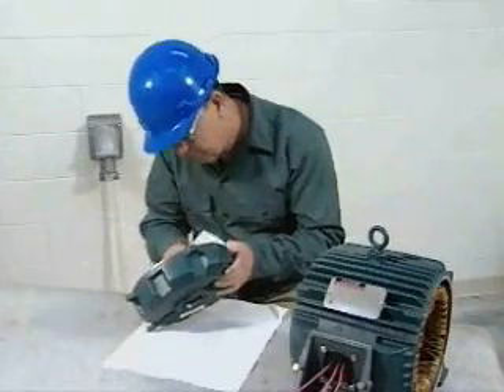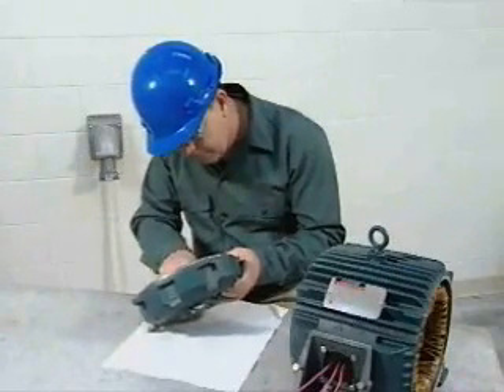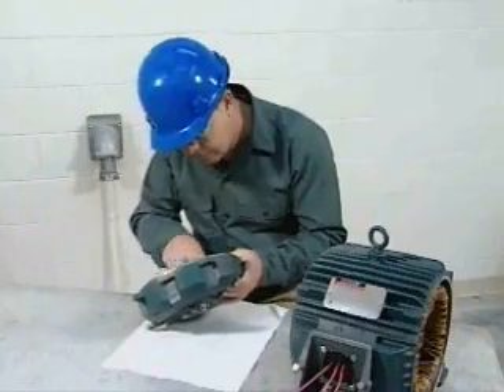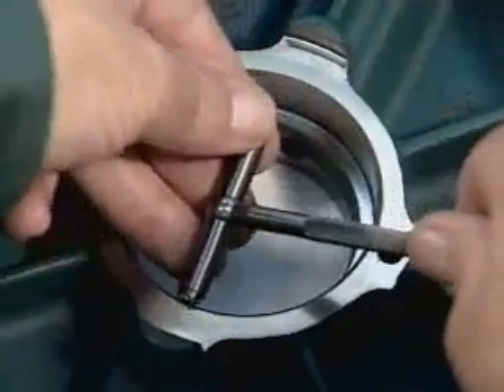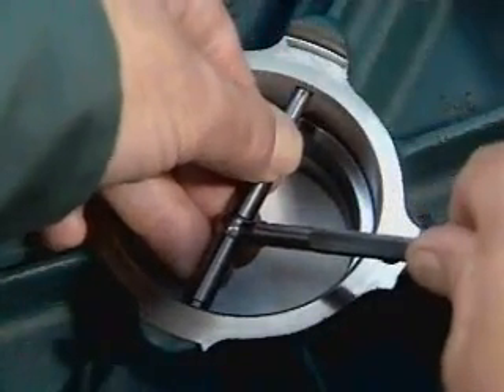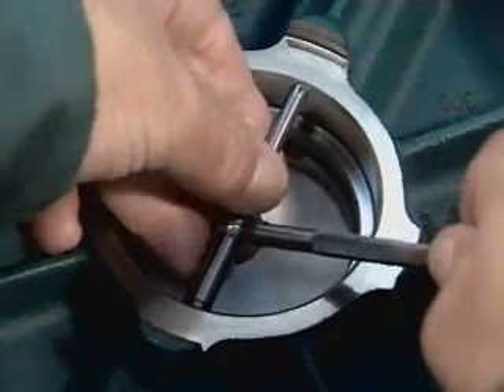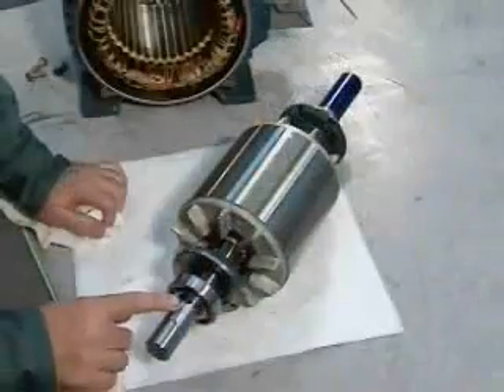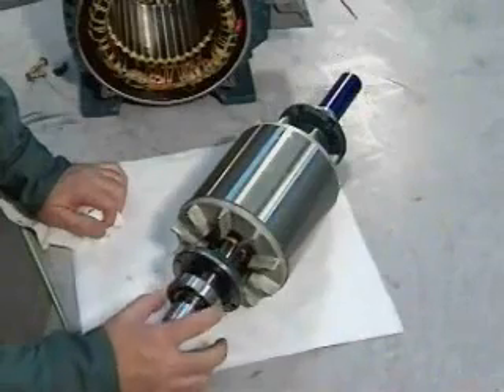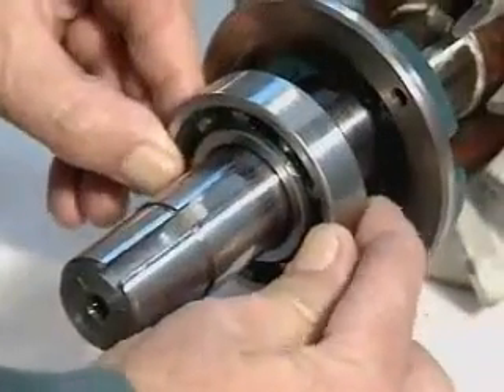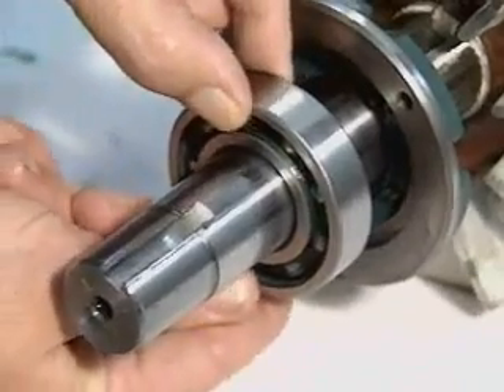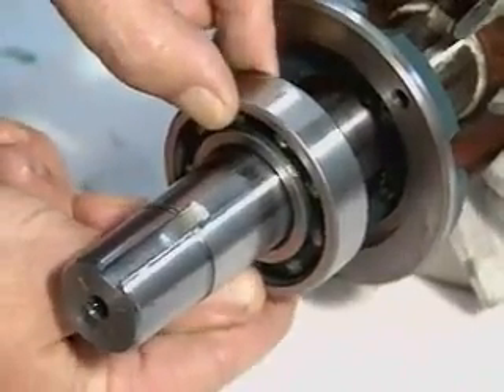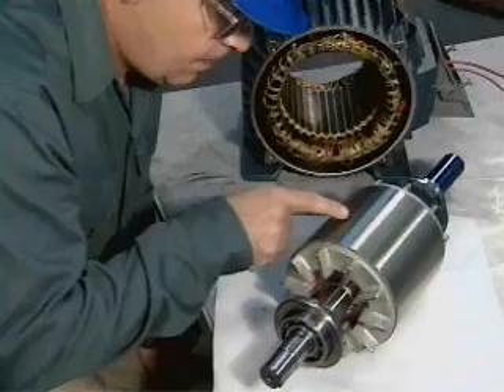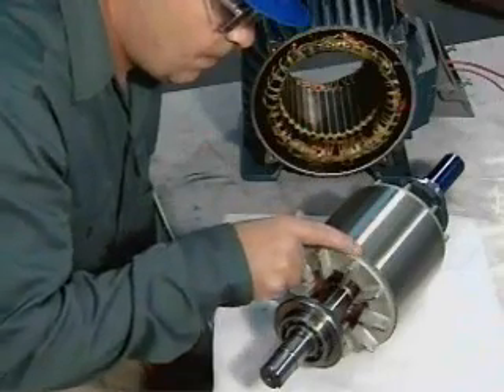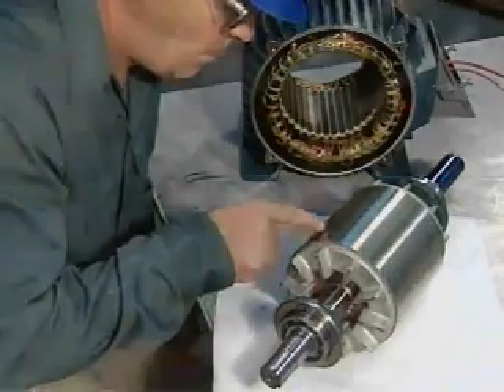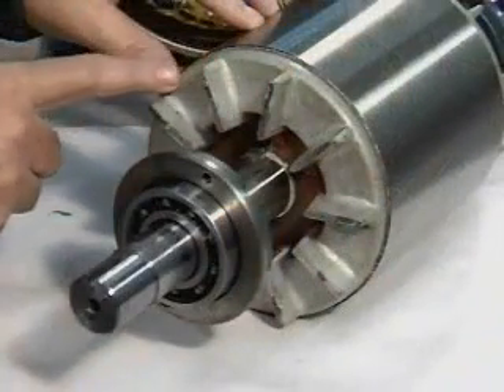Once you have disassembled your motor, you're ready to inspect and clean the parts. Wipe the end bells with a soft, lint-free cloth. Inspect them for cracks and other signs of damage. Check the bearing seating surfaces of the end bells to determine if they are out of round, tapered, or worn. Inspect the shaft and bearings for signs of damage. If the bearings are bad, they will need to be replaced. Inspect the rotor for loose or broken bars, end ring damage, and overheating. Inspect the rotor fins for signs of damage.